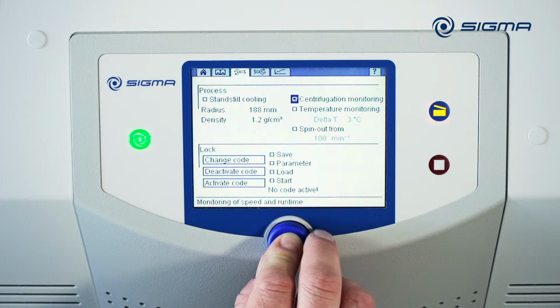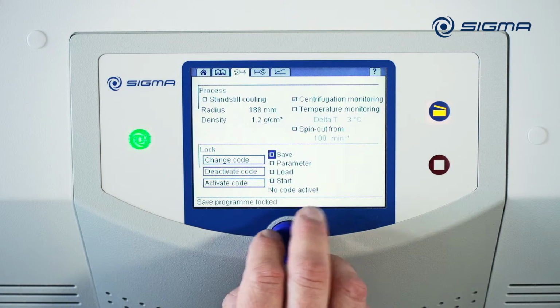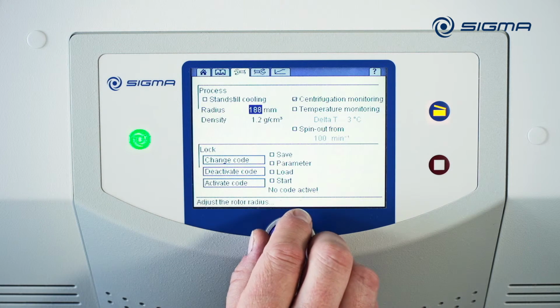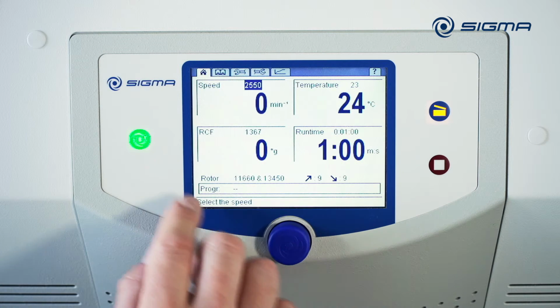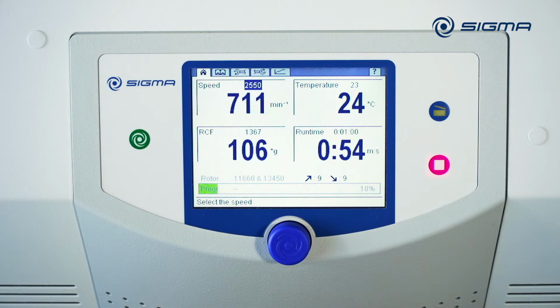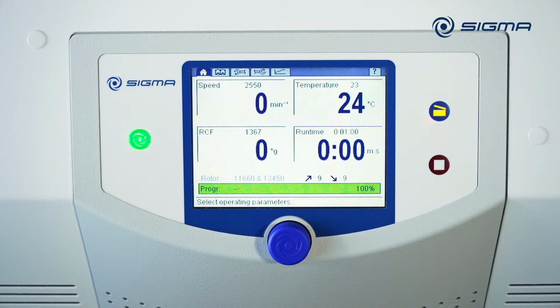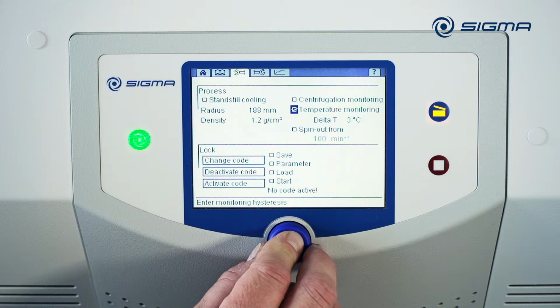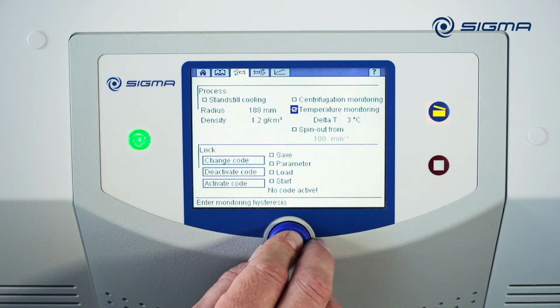If you enable the Centrifugation Monitoring option, the centrifugation run is continuously monitored, and a message appears on the screen at the end of the process. If the temperature monitoring option is enabled, the centrifuge can only be started when the difference between the set point value and the actual value does not exceed 3 degrees Celsius. The allowable temperature range can be preset. If the centrifuge leaves this temperature range while running, it will brake in order to protect the product.